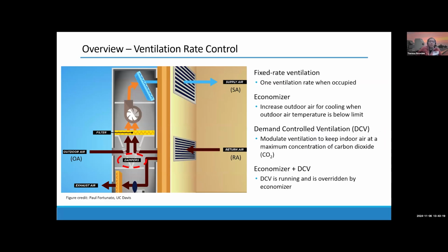And so what this project is about is thinking about how we control the ventilation rate in a packaged HVAC system. And then the simplest implementation, the ventilation rate will be fixed. Essentially, this damper is in some fixed position. So when the return air mixes with the outdoor air and then goes to the supply air, we'll have essentially a constant outdoor air fraction.